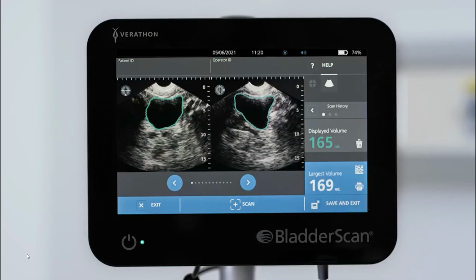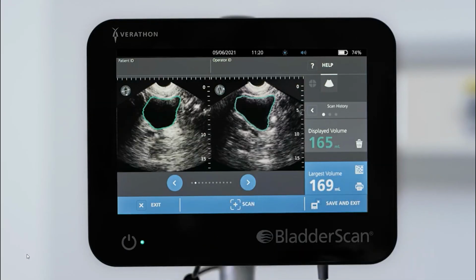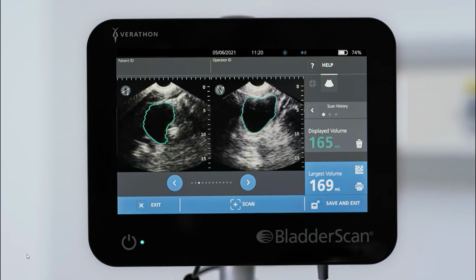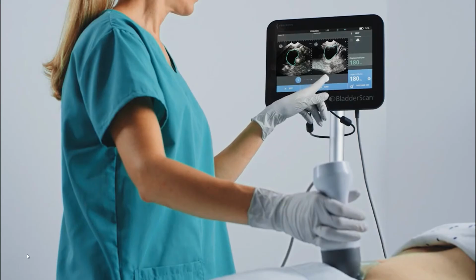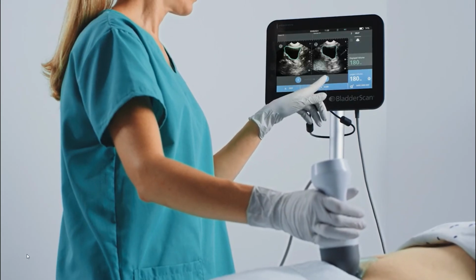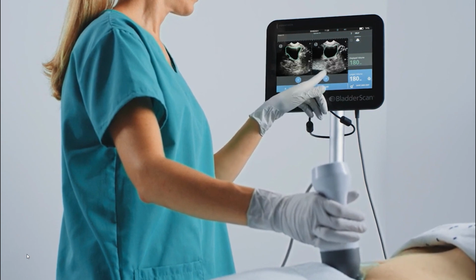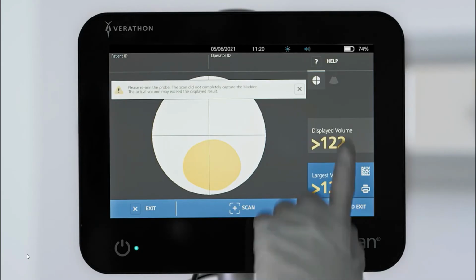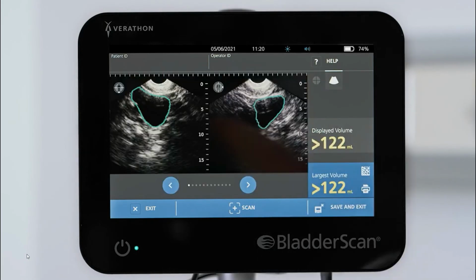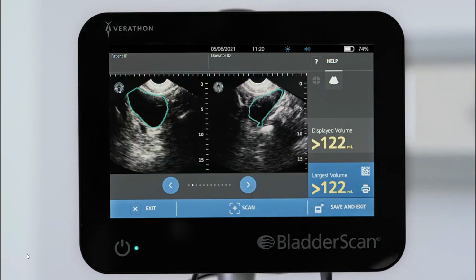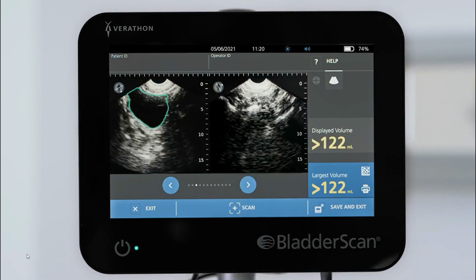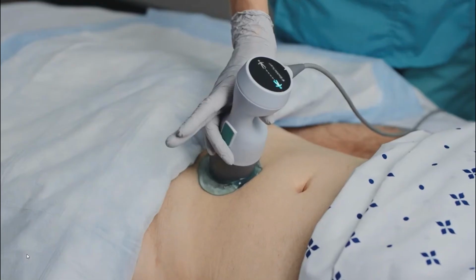For more detail, you can press the B mode icon to scroll through pairs of individual ultrasound images that were captured during scanning. Typically on good scans, the green bladder outline is completely visible in all images of the bladder. The bladder was not in full view during the scan. Some of the individual images may show an edge of the bladder clipped off, or the bladder image may be missing. If the volume number is yellow, scan again to improve the results.